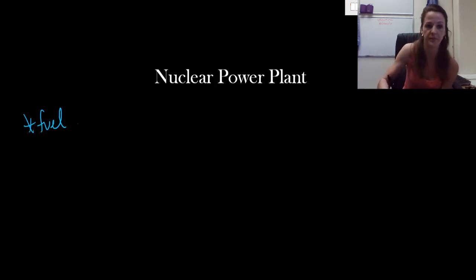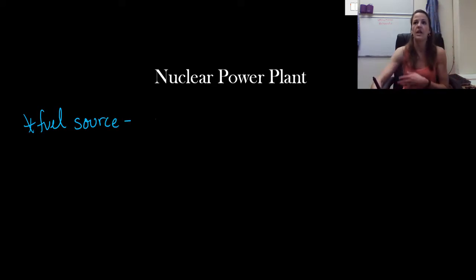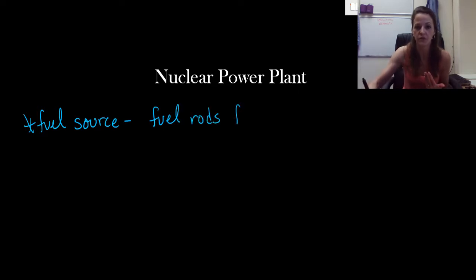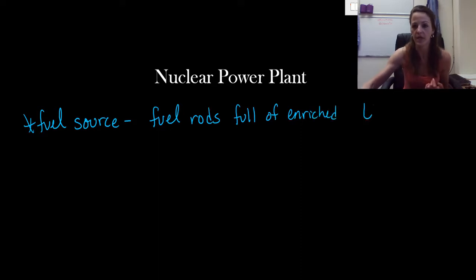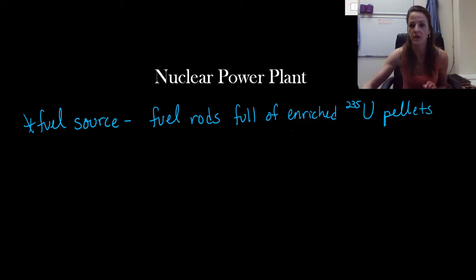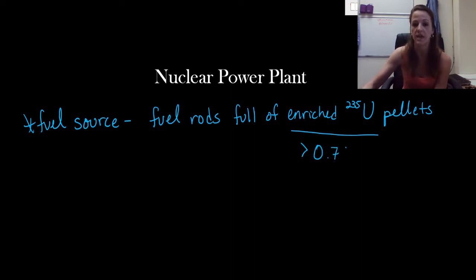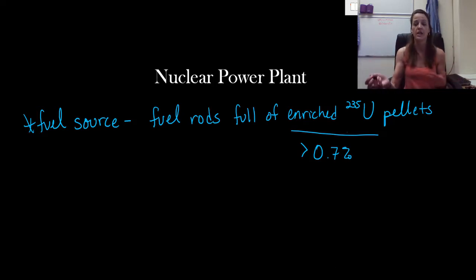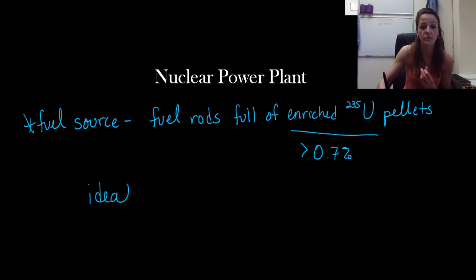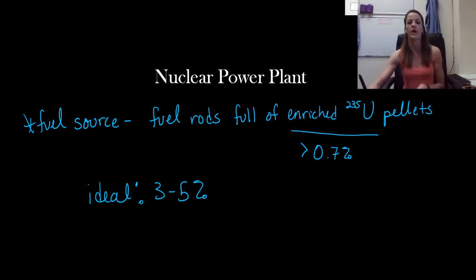Our fuel source is basically a bunch of different little pellets that we store in things called fuel rods — fuel rods full of enriched uranium-235 pellets. Enriched uranium-235 by definition means that it has greater than 0.7% of U-235. Usually the fuel source is uranium-238, but for a power plant, our ideal fuel source is actually anywhere between 3% to 5% enriched uranium.